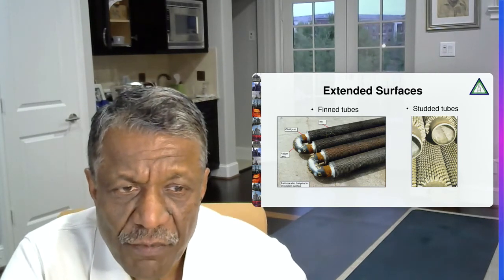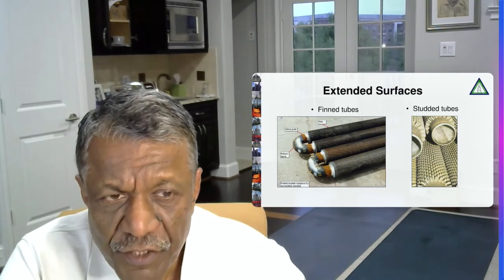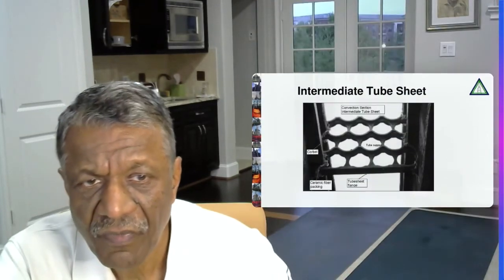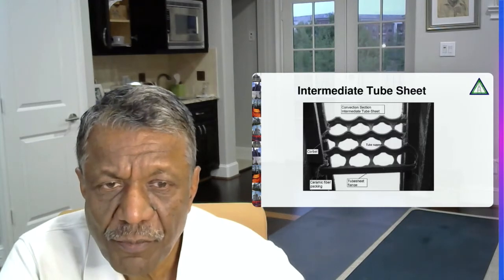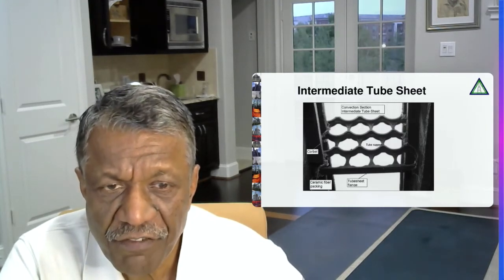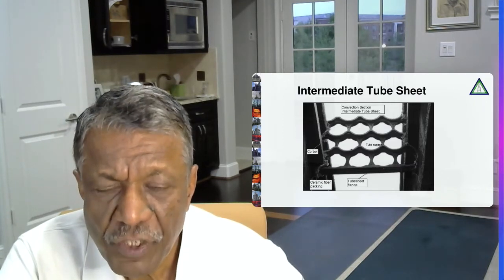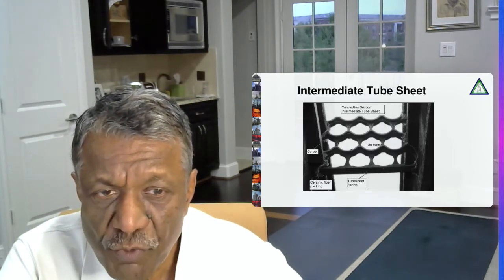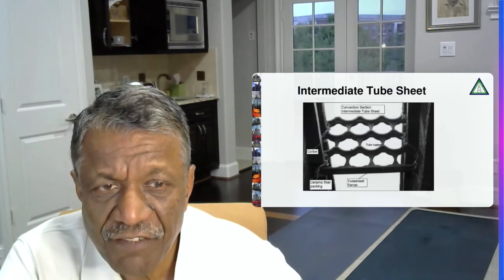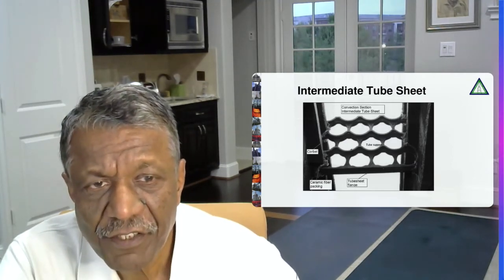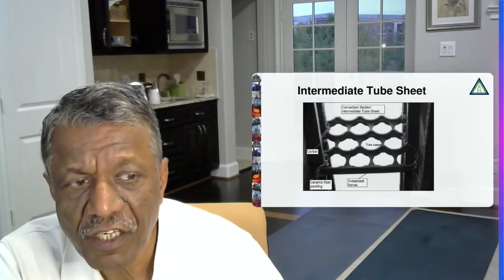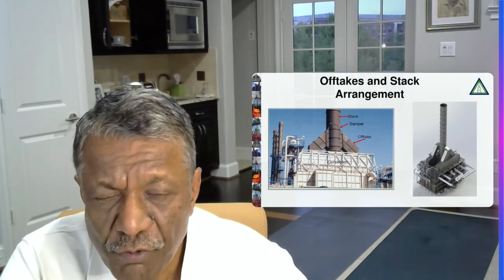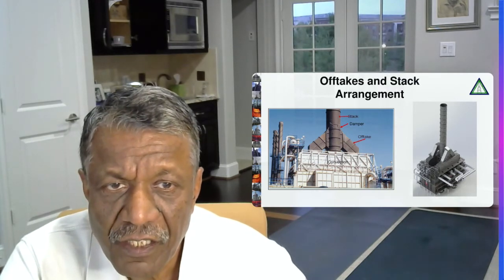Same thing with the studded tubes. Studded tubes are very sturdy and they are mostly used for oil firing because they are easier to clean. The horizontal tubes, they need to be supported every 35 diameters or 20 feet, whichever is maximum, and to keep them straight. So this is a picture of an intermediate tube sheet. These tube sheets are made out of high chrome nickel alloy because they see the high flue gas temperatures. So they are pretty expensive and important component in the fire heaters.